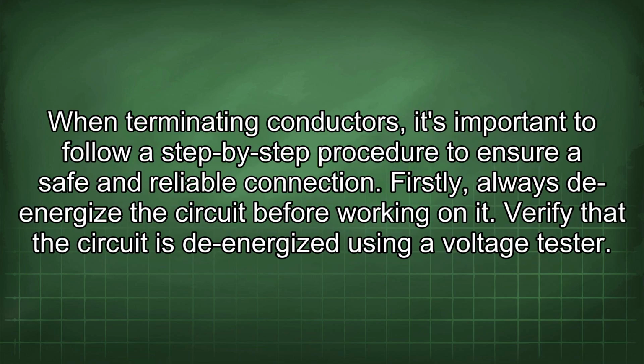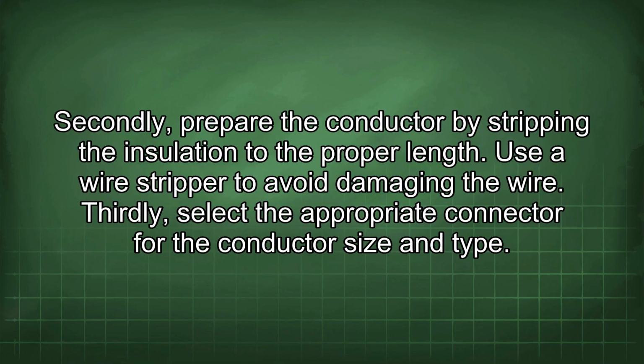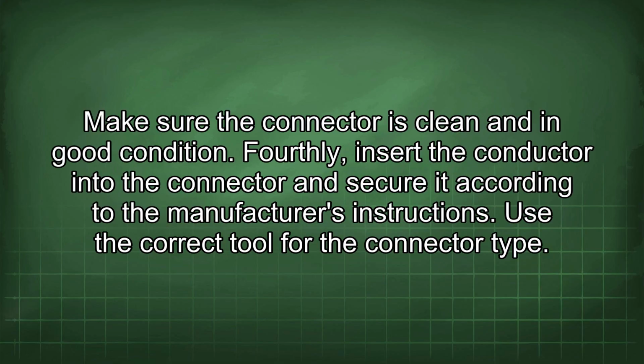When terminating conductors, it's important to follow a step-by-step procedure to ensure a safe and reliable connection. Firstly, always de-energize the circuit before working on it. Verify that the circuit is de-energized using a voltage tester. Secondly, prepare the conductor by stripping the insulation to the proper length. Use a wire stripper to avoid damaging the wire. Thirdly, select the appropriate connector for the conductor size and type. Make sure the connector is clean and in good condition.